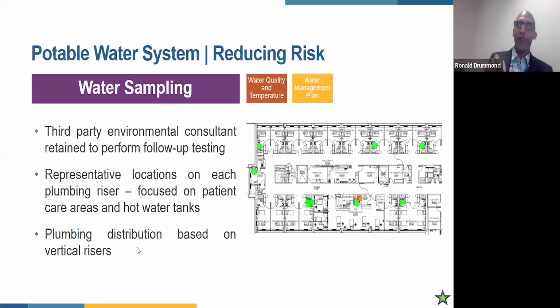And for this reason, if we do get hit, and Jess touched on this, we will test the areas that are adjacent to it. This means above, below. It could mean 2 floors above, 2 floors below, but we also test those adjacencies as well. So once it comes up, we know it stubs off and feeds at least one washroom. Often there's a couple more washrooms that are on there, or kitchenette, that sort of thing. So all the areas that are connected, we try to sample those at that time.